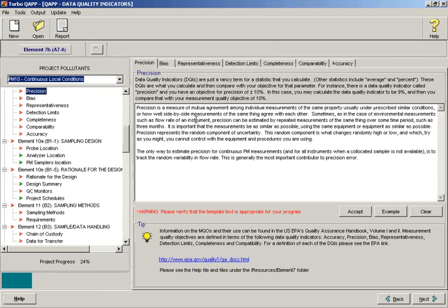Data quality indicators, so really great stuff like precision. And then you talk about precision in general, and there's another link here about definitions. But what does this mean in terms of my TEOM? So I've got specific text in here that applies to doing continuous PM10 monitoring and how precision applies to that particular measurement, because depending upon whether you're making many measurements with a similar piece of equipment or you've only got one piece of equipment, how are you going to measure precision?